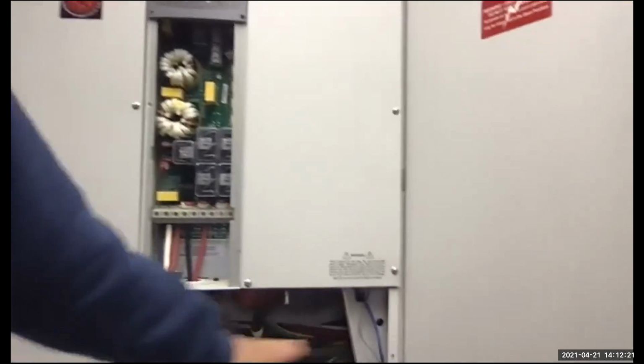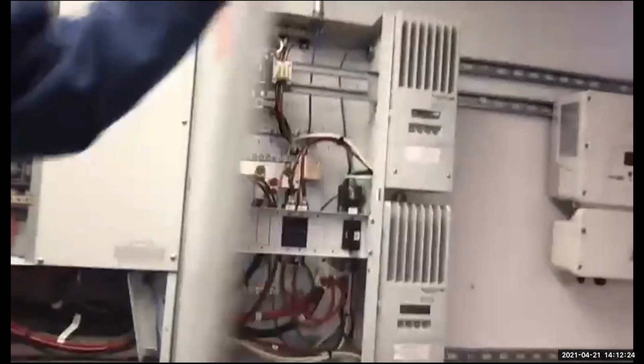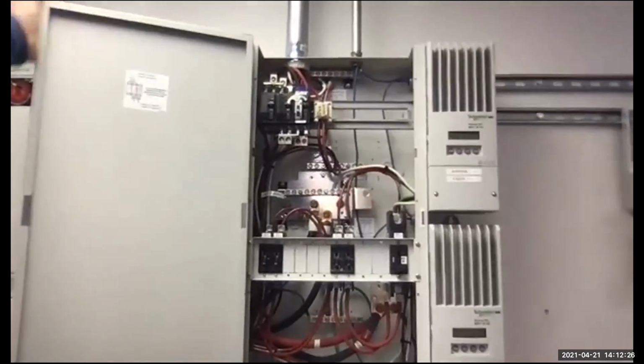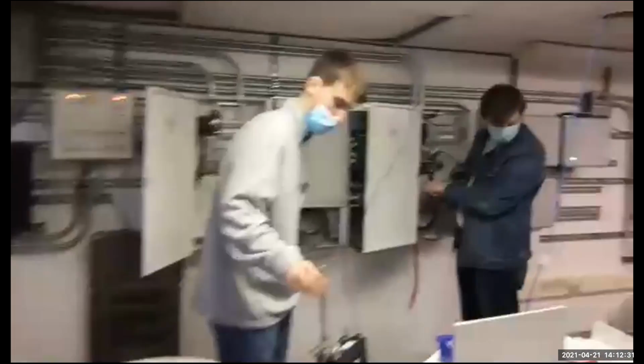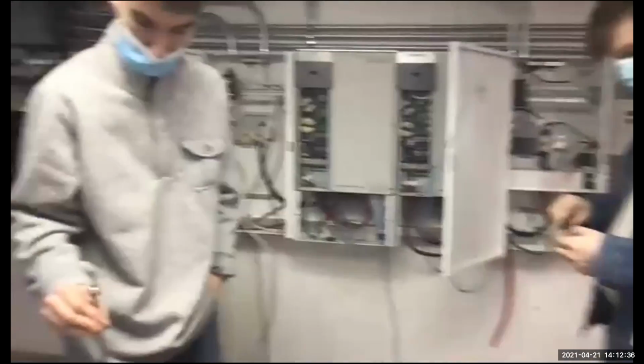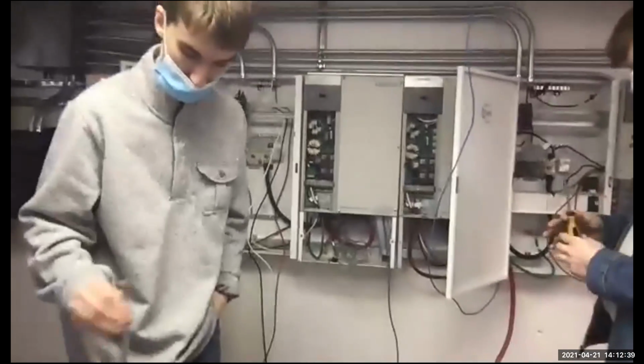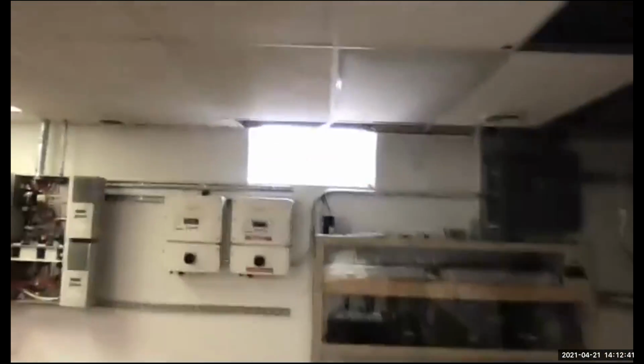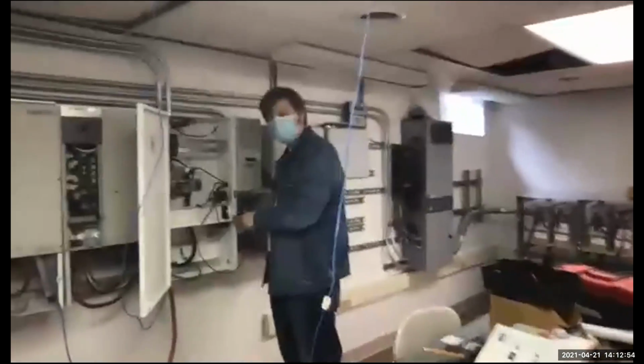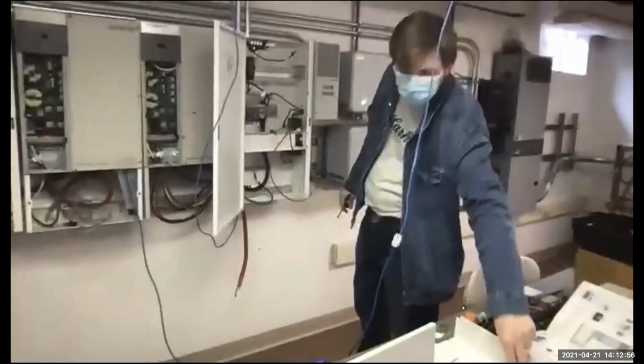So now we're bringing all those cables in. We know we got those batteries. We know that's what we need to do. We know that's why that is there. So let's check on these guys. How you doing over here? Pretty good. So if I only want one of these, can I just get rid of the 175? Well, what about this thing right here? You need this bar. Come over here. The bar is right there. You just don't need the breaker attached to it. Oh, I see. Okay. Gotcha. Make sense? That bar allows us to bring in multiple things to this one breaker.